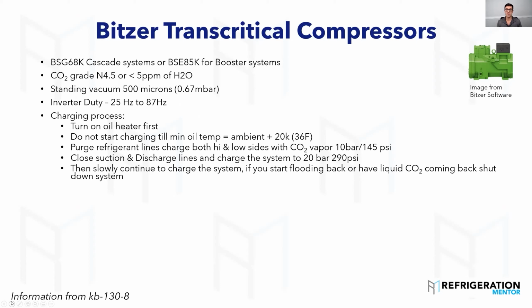Do not start charging until the minimum oil temp is equal to ambient plus 20K, or 36 Fahrenheit. So if the ambient, for example, is 20 Celsius, they're looking at 40 Celsius oil temp, or 36 on top there. So if it's 60 out, it should be 96 oil temp. I haven't seen this. This is not in the Copeland guides, but this is a good way to check.